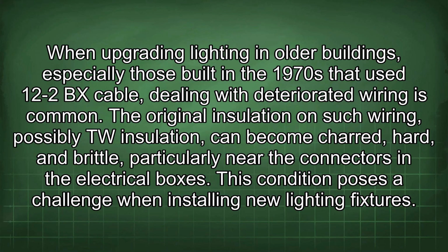When upgrading lighting in older buildings, especially those built in the 1970s that use 12-2BX cable, dealing with deteriorated wiring is common. The original insulation on such wiring, possibly TW insulation, can become charred, hard, and brittle, particularly near the connectors in the electrical boxes. This condition poses a challenge when installing new lighting fixtures.